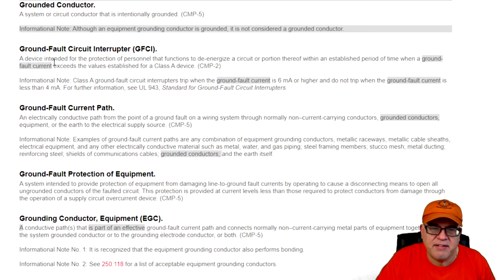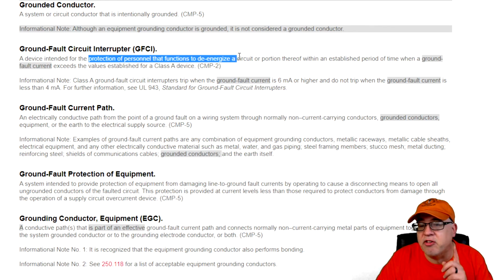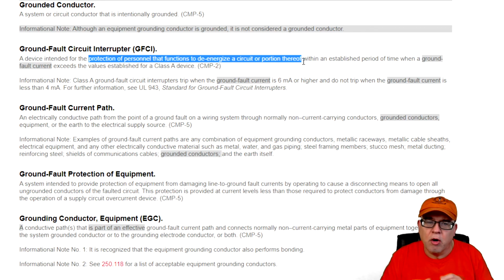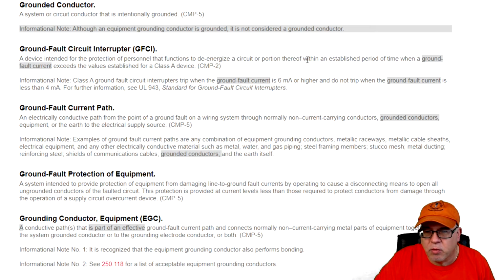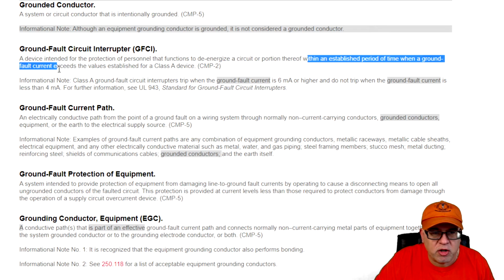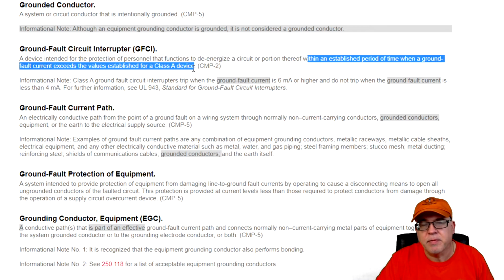But again, it's a device intended for the protection of personnel that functions to de-energize the circuit or portion thereof, because it could be a breaker, it does the whole circuit, or it could be a device that does the portion downstream of it, okay, where necessary, depending on where 210.8 or other areas of the code tells you to put a GFCI, okay. It says within the established period of time where a ground fault current exceeds the values established for a Class A device. So we refer to this as a 5 milliamp, okay, milliamp nominal.